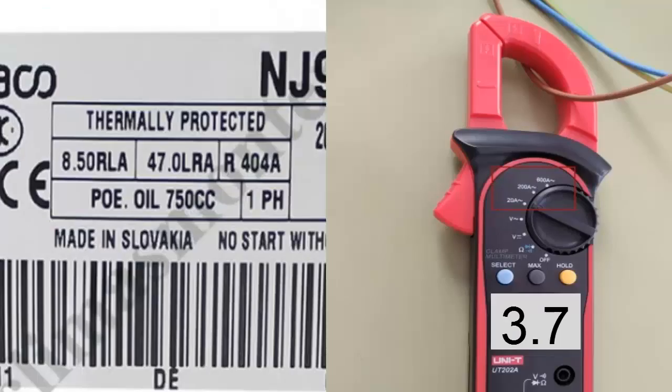Step 3. If the equipment is lacking refrigerant, one of the symptoms will be a decrease in electrical consumption measured by the amperometric clamp.